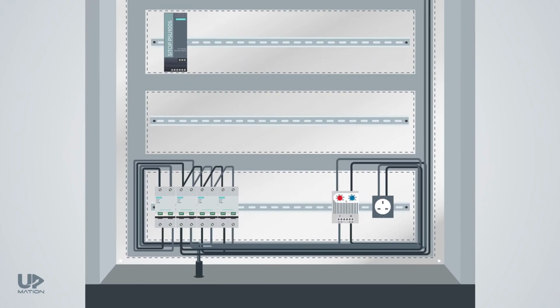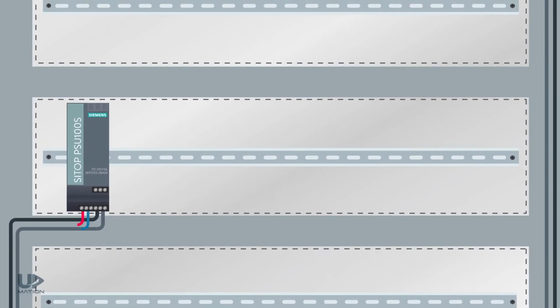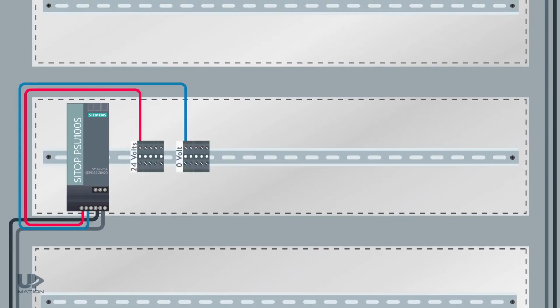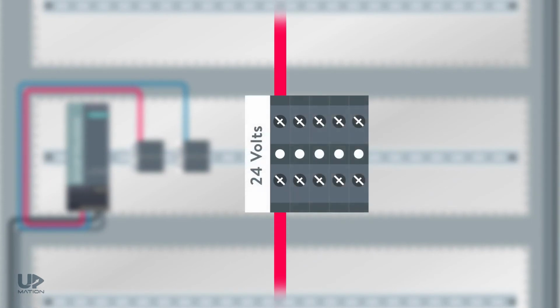The next step is to connect the 120 volts to the power supply. Take the 24 volts from its output and distribute it over some terminal blocks. As you may know from our previous videos, by using a terminal block, you can join two wires to each other. To connect all of the terminal blocks of the same purpose, we can use a terminal strip jumper. I should put it in the middle holes of the terminal blocks and fasten its screws. In this way, all of these terminal blocks will have the same voltage of 24 volts.